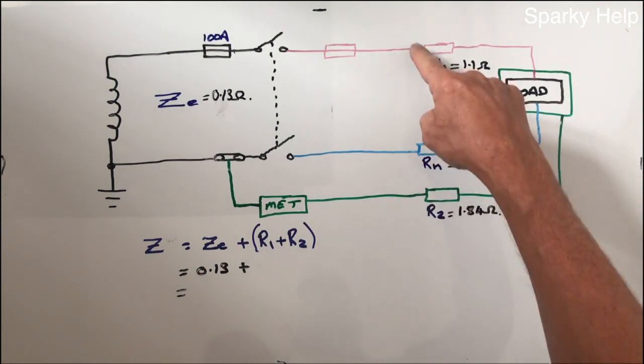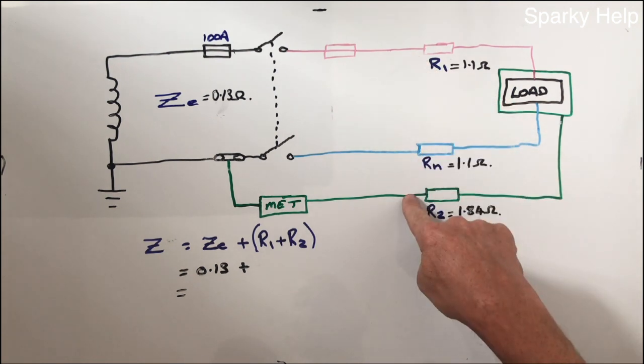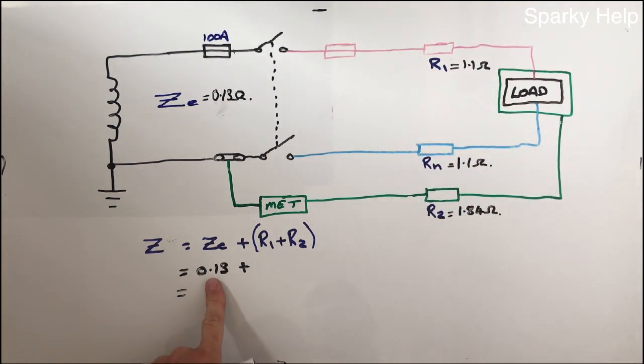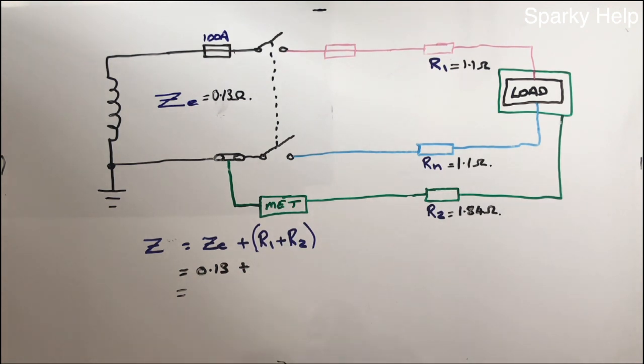So we want to do a fault which would be midway. How much fault current would flow if we had midway between these two points? So ZE will remain unchanged, because we have nothing to do with that. The bit that is going to change is R1, R2, so because resistance is proportional to length, we need to divide this answer by 2. So we have 1.1 plus 1.84 and we divide, I put this in brackets, divide this bit by 2.